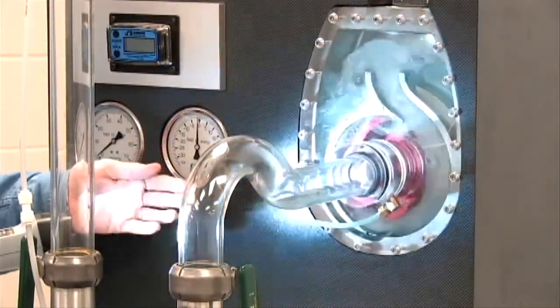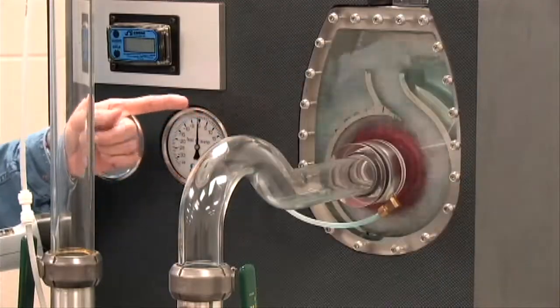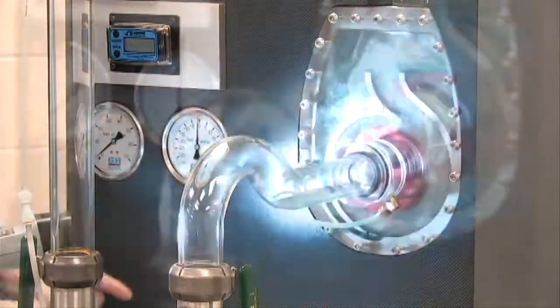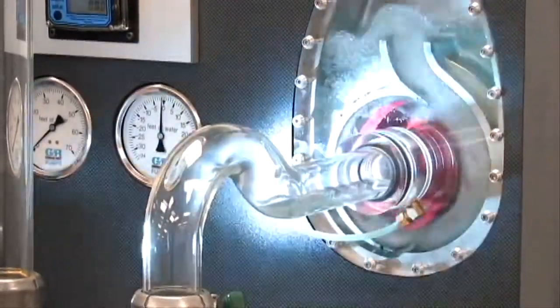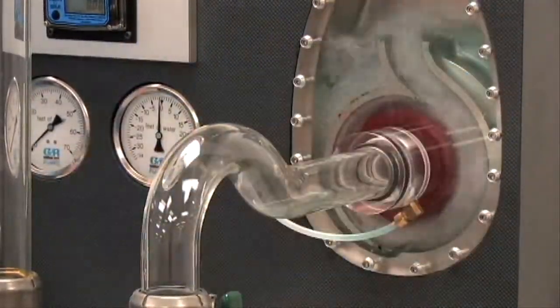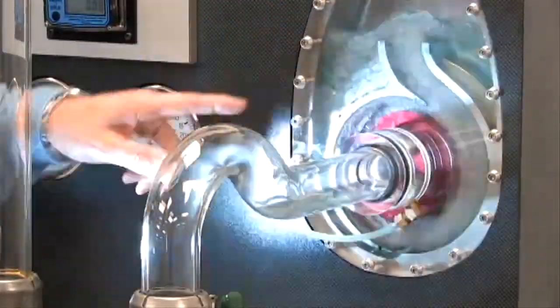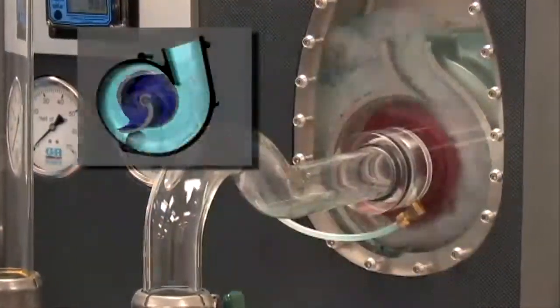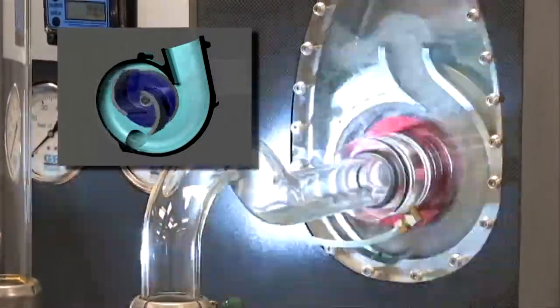After we fill the volute casing with water and we energize the pump, the impeller turns in a counter-clockwise rotation. The initial prime of the pump is slung through the volute scroll, or the ever-increasing water channel, into a pressure cavity or discharge chamber inside the volute. Inside this discharge chamber, the air and water separate.